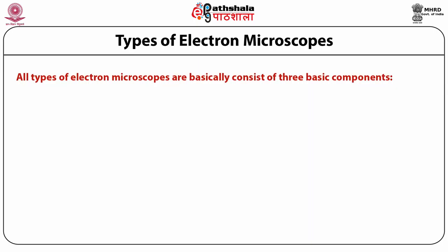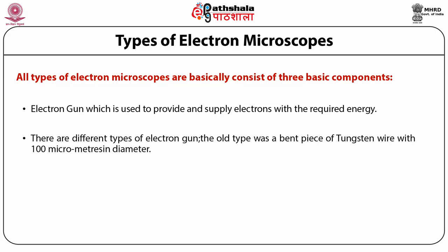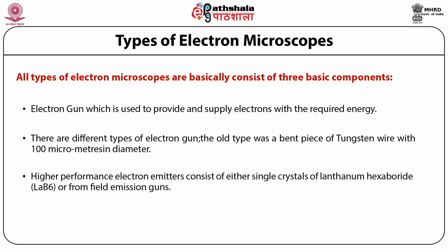Since electrons are easily scattered, all electron microscopes should operate under high vacuum. All types of electron microscopes basically consist of three basic components. The electron gun, which is used to provide and supply the electrons with the required energy. There are different types of electron gun. The old type was a bent piece of tungsten wire with 100 micrometers in diameter. Higher performance electron emitters consist of either single crystals of lanthanum hexaboride LaB6 or field emission guns.